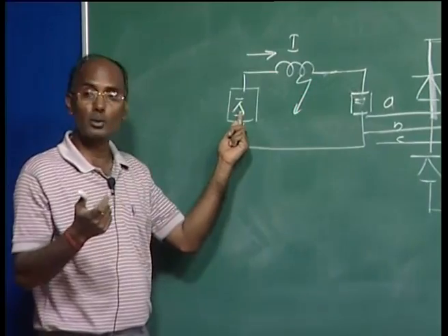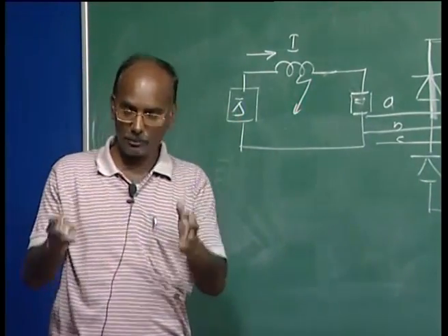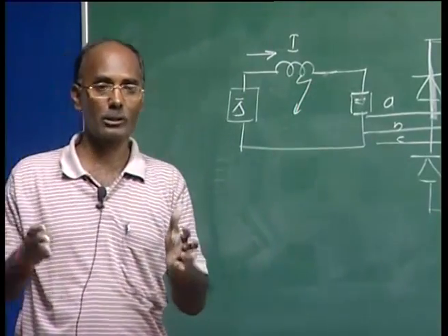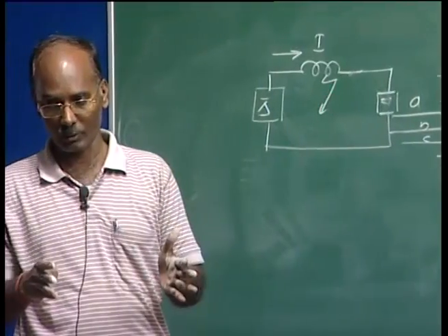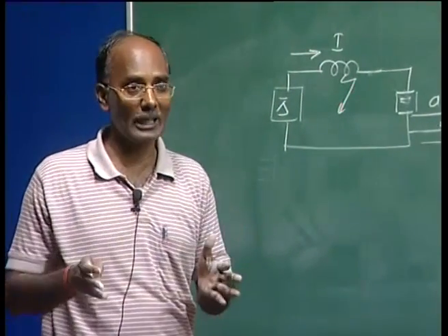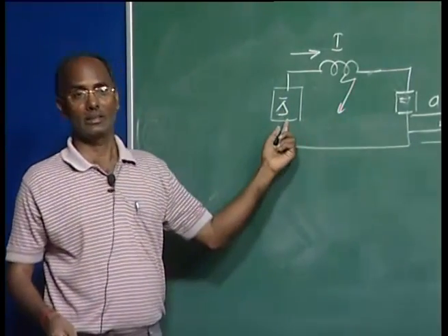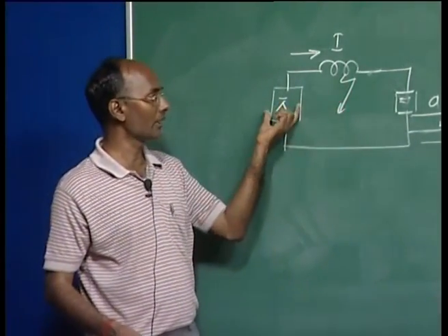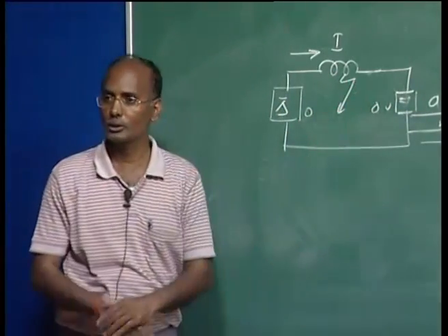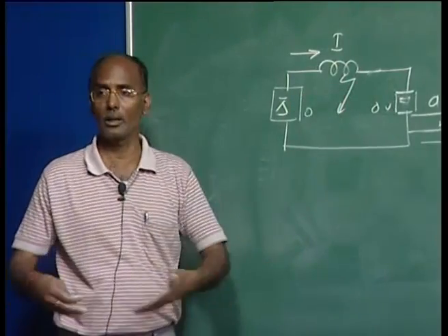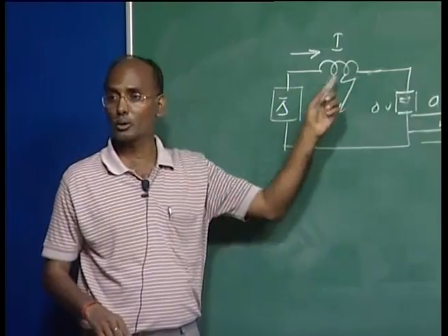And you know, this control is very, very fast. Even your mechanical system like a circuit breaker requires several cycles, 3 to 4 cycles, for complete operation of a fault, opening of the line, it requires 3 to 5 cycles. In less than that time, these controllers can act. And if a fault is there, they can operate at zero potential. Now with this 0 volt, the fault is gone. Then you can inspect where the problem is, and then again you can go for restart. So we do not use any circuit breaker here.